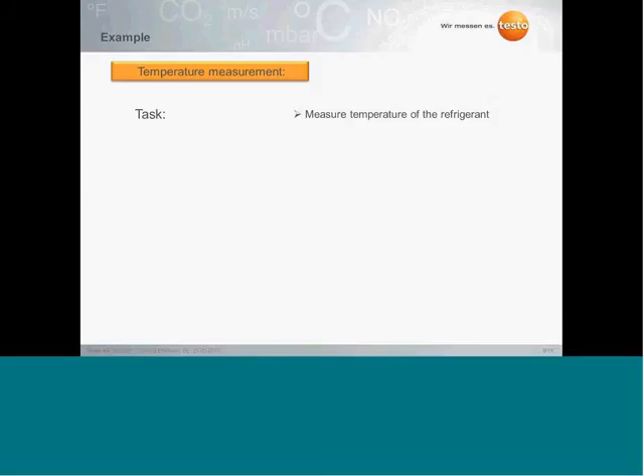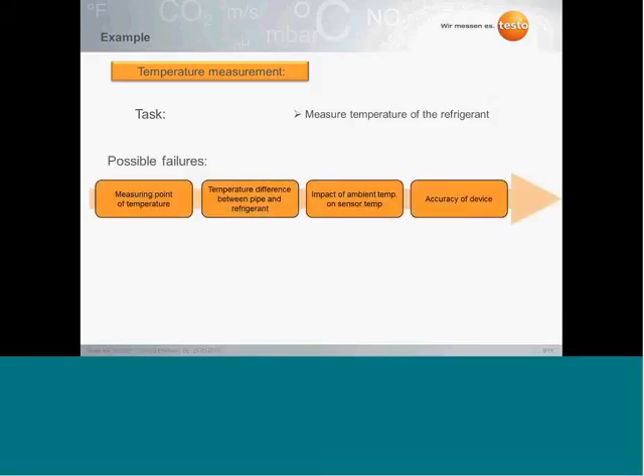To come to our subcooling and superheating, of course, we have to measure the temperature of the refrigerant. As possible failures, we have firstly the measuring point. Do we measure the temperature at that point where we really want to know it? And secondly, there's always a temperature difference between the pipe, which we are actually measuring, and the refrigerant inside. Depending also on the outside temperature, we have an impact of the ambient temperature. Because every time you measure temperature, you only measure the temperature of a sensor element.